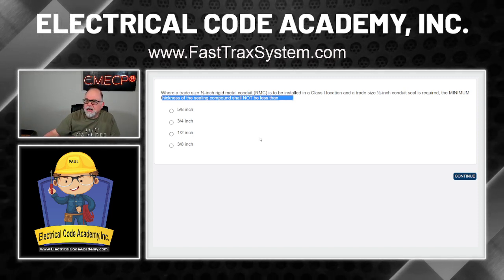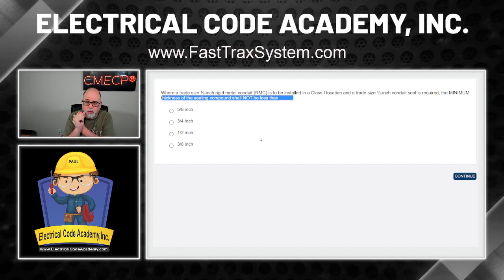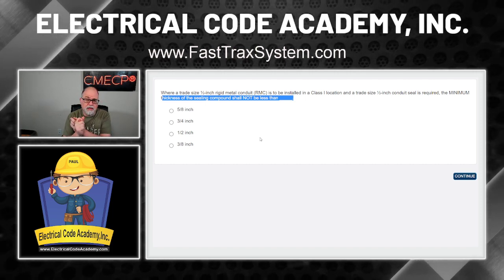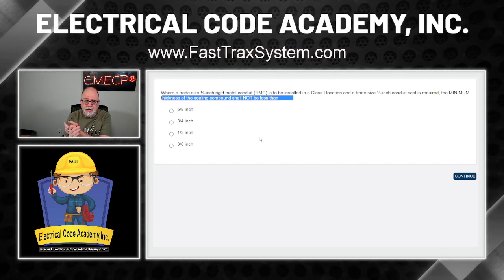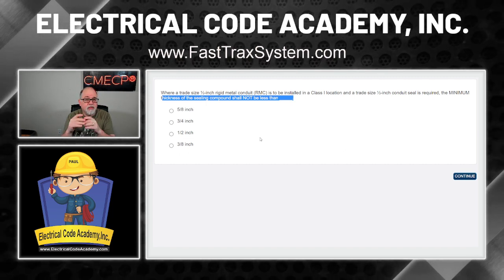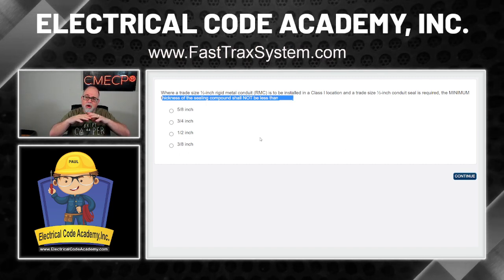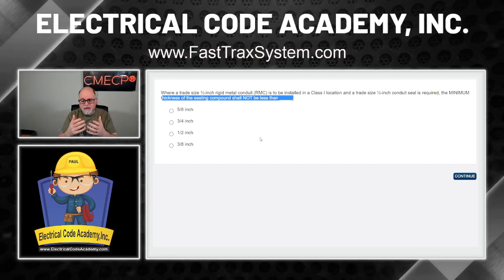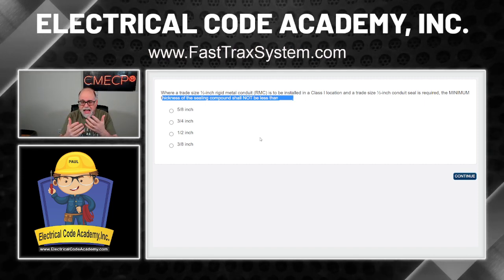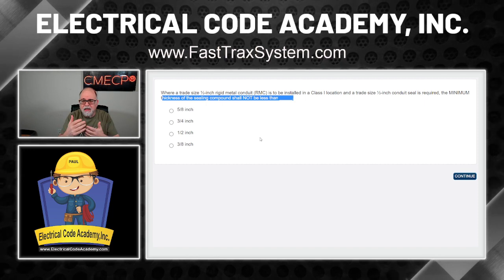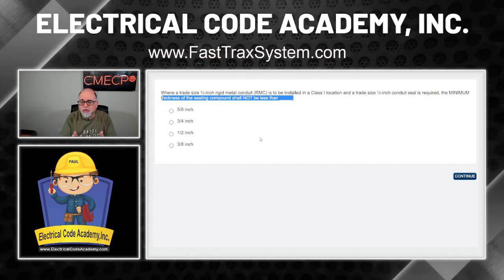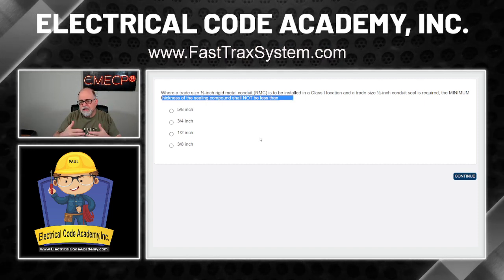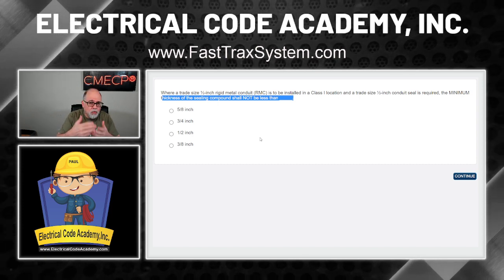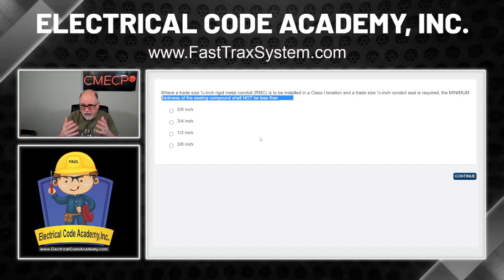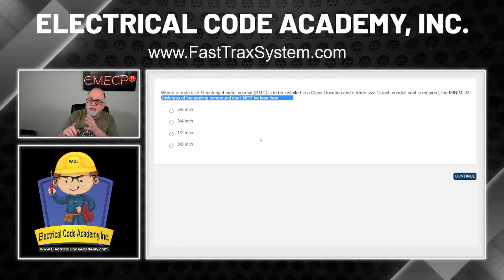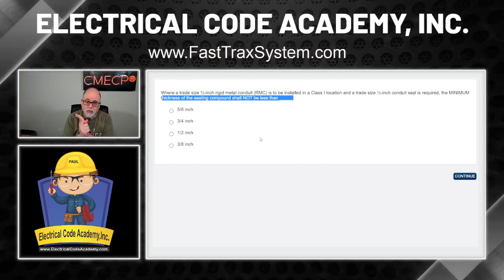So the first thing that I look at and it triggers for me is it's Class 1. All right, so you need to know the article that deals with Class 1. That's Article 501. Okay, hazardous location starts at 500. That's what gives you all of the things that constitute the different types of gases and all this, and their classification. Gives you some general rules. And then you start getting into Class 1, Class 2, Class 3, which is 501, 502, 503, that type of thing. So in our case, we know it's Class 1, so that's 501.